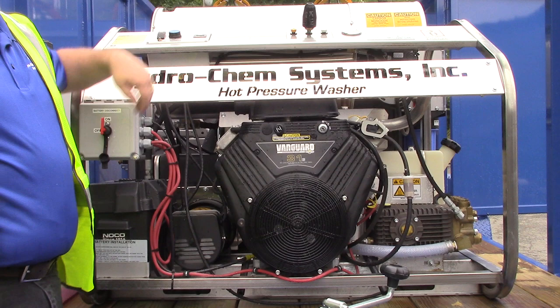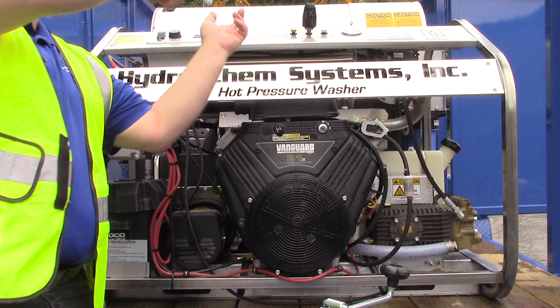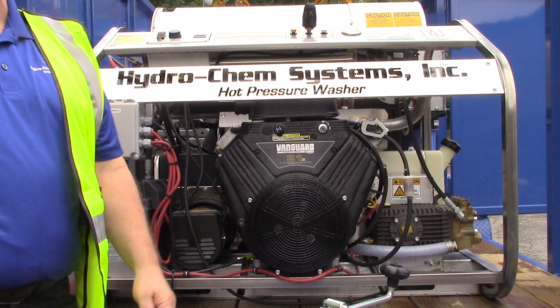That's a GFI plug in there? The GFI plug is on the backside with a reset, so it's easy enough. What we did with the light is just more communication. If somebody calls in and says their vacuum motor is not running — are the lights on? Yeah, lights are on. Maybe it's a flow switch inside the tank, or the tank could be full. So it's a really good diagnostic tool for all of us.